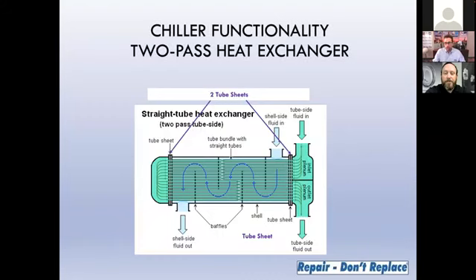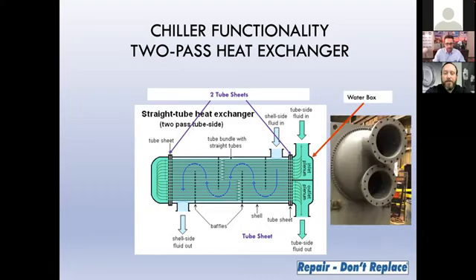This webinar will focus on heat exchanger and chiller corrosion related issues. Most of the time we work on condensers because they're part of an open loop system with the cooling tower. And this slide depicts the operation of a standard two-pass condenser, which is the most common type of condenser that we see in the field.